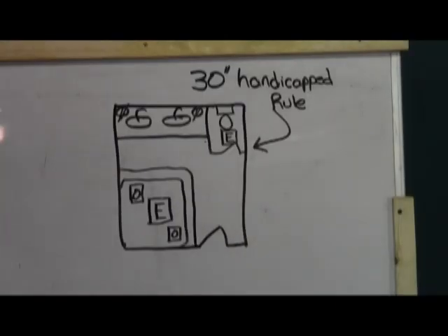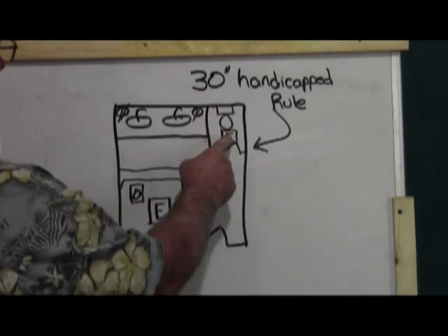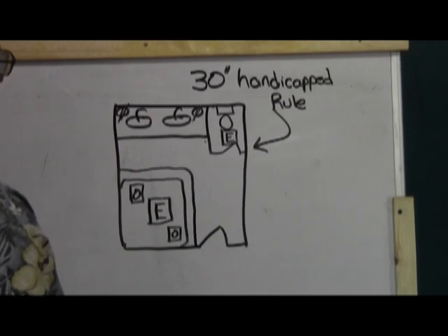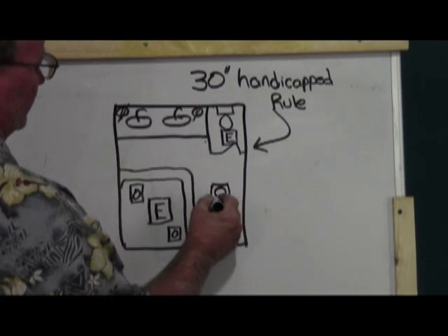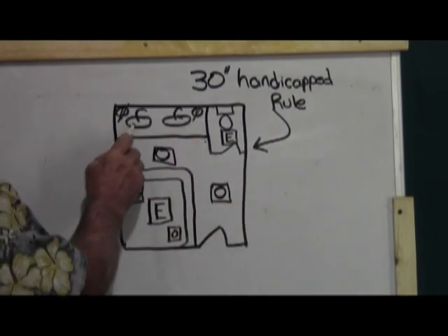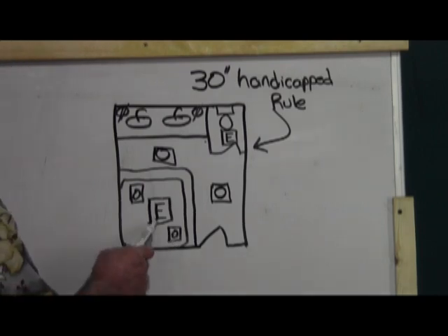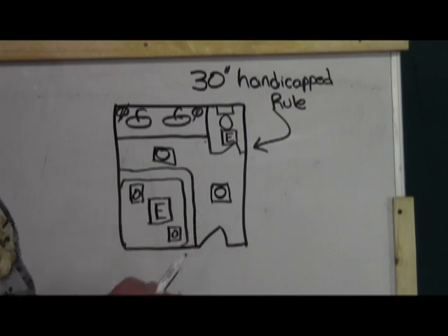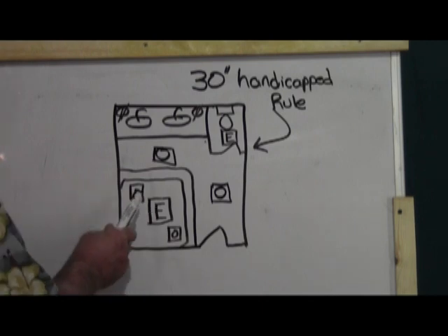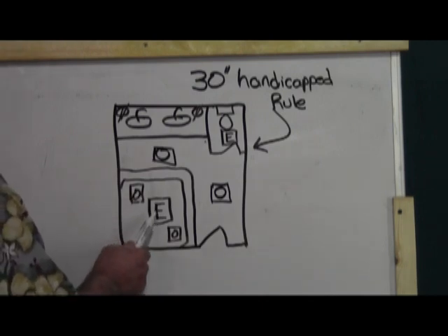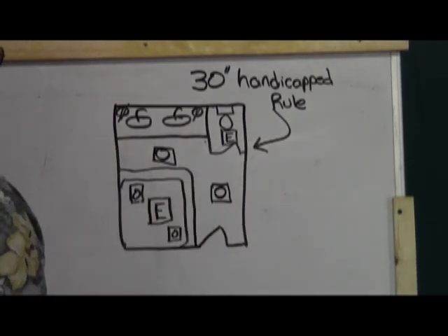In this next scene we see a recirculating tub. Basically you have your water closet, you have 2 sinks, your lighting is probably going to want to be can lights. You must have 1 outlet per basin, okay, and you're probably going to want can lights for your electro massage bath, whatever. And you also are probably going to be required to have an exhaust fan above it, even if you have a window. Same here, good to have an exhaust fan.